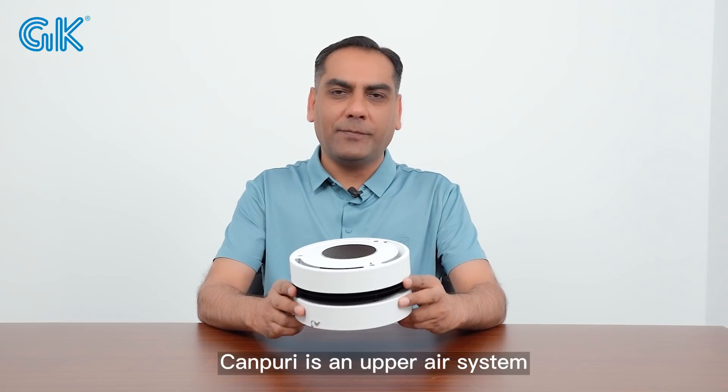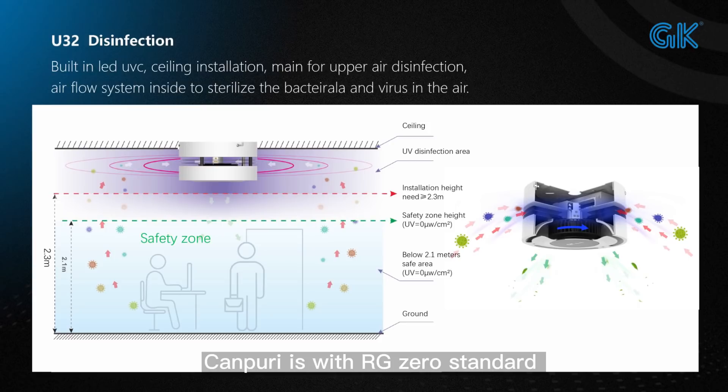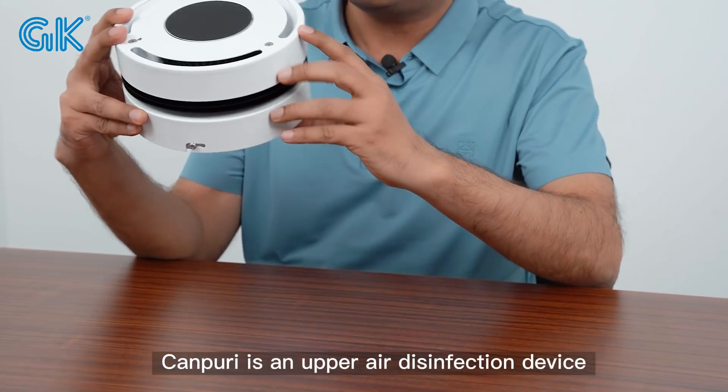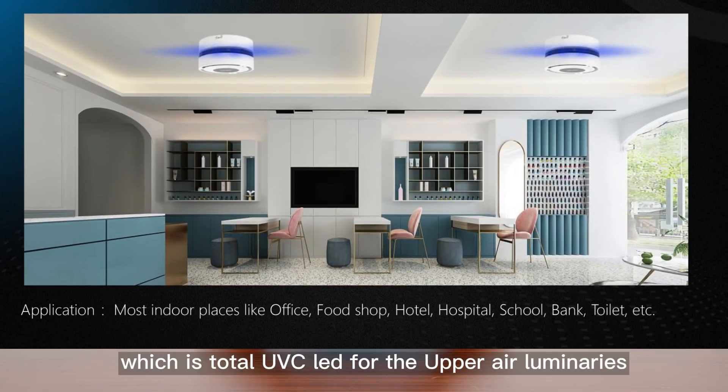Canpuri is an upper air system with China and US patent design. Canpuri meets RG0 standard when the height is under 2.1 meters, and the installation height should be 2.3 meters. Canpuri is an upper air disinfection device for occupied rooms, which is a total UVC LED upper air luminaire.